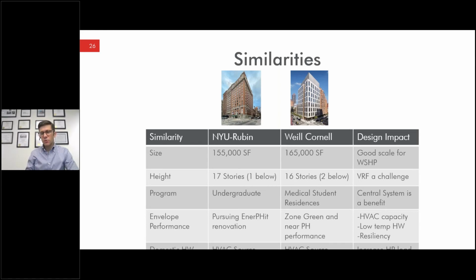That allowed us to reduce and minimize our HVAC capacity and how many heat pump modules we needed. It also allowed low temp hot water to be pretty achievable at the perimeter, so we didn't have concerns with the heat we were getting out of that water. The Weill Cornell building uses a valence unit system, which needs that envelope to be pretty high performance for the systems to work, so that was a consideration.